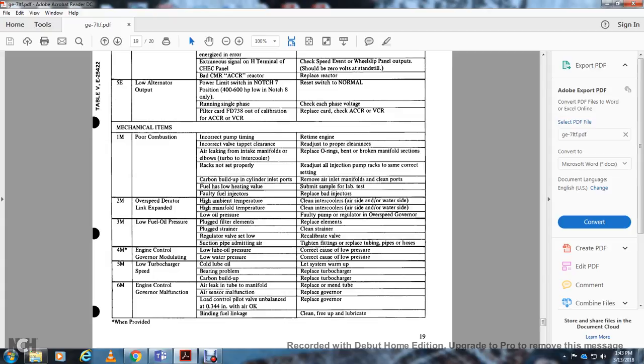All right, mechanical item 2M, overspeed derator, link expanded. High ambient temperature: clean intercoolers, air side and water side. High manifold temperature: clean intercoolers, air side and water side. Low oil pressure, faulty pump with regulator, overspeed governor. 3M, mechanical, low fuel oil pressure: plugged filter elements, replace element. Plugged strainers, clean strainer. Regulating valve set low, recalibrate valve. Suction pipe admitting air, tighten fittings, and replace tube piping and hoses.